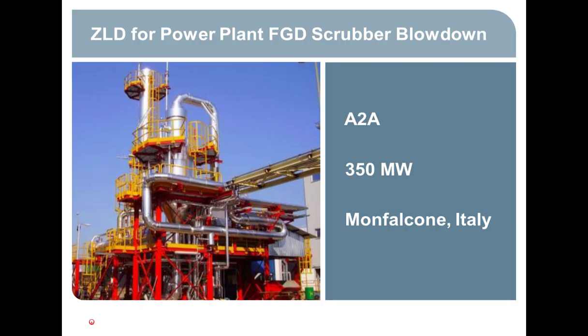We talked about cooling tower blowdown in power plants. The other big item which we want to talk about is FGD scrubber blowdown. These are not very common. There's only a few of these in the world. Most of them are in Europe and China, and there's only one or two here in the U.S. Again, the idea is to take FGD purge water and eliminate the discharge completely. So here's a plant in Italy that does that, a coal-fired plant.